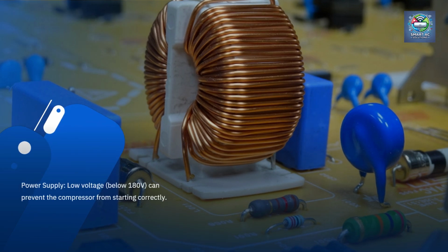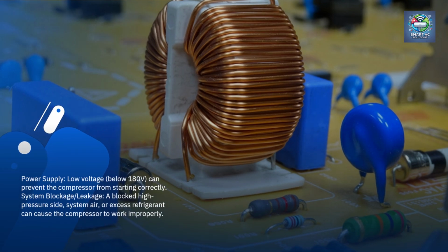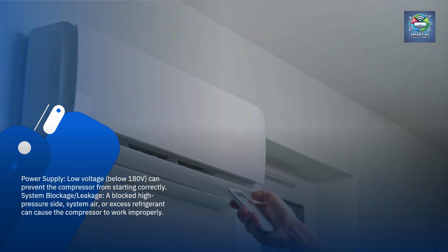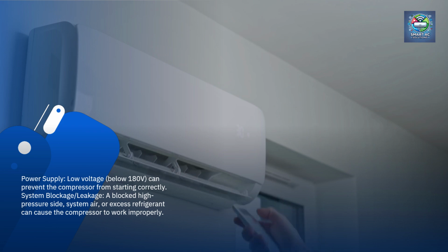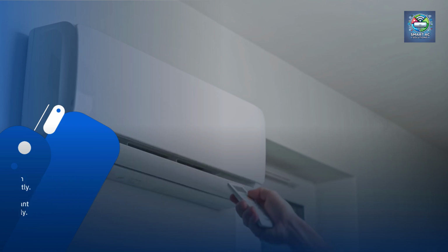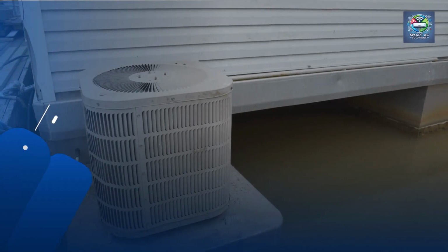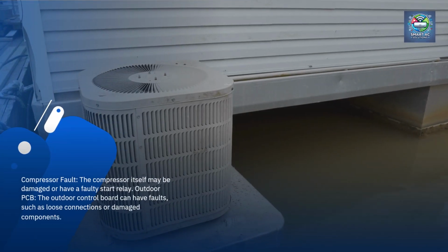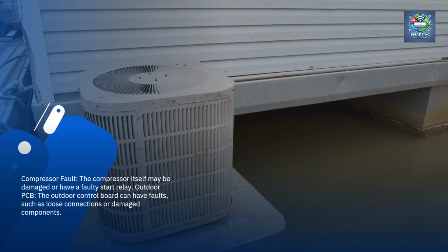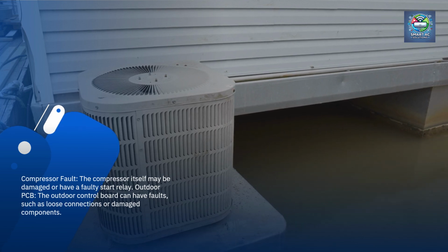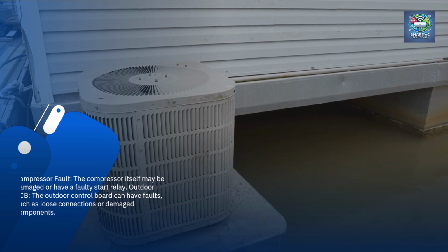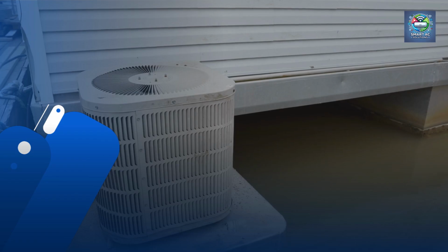Power supply. Low voltage, below 180 volts, can prevent the compressor from starting correctly. System blockage, leakage. A blocked high-pressure side, system air, or excess refrigerant can cause the compressor to work improperly. Compressor fault. The compressor itself may be damaged or have a faulty start relay. Outdoor PCB. The outdoor control board can have faults, such as loose connections or damaged components.